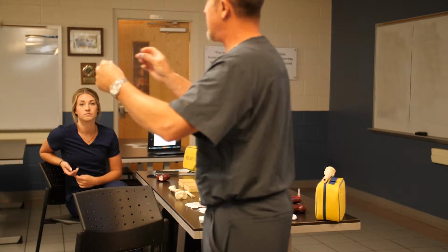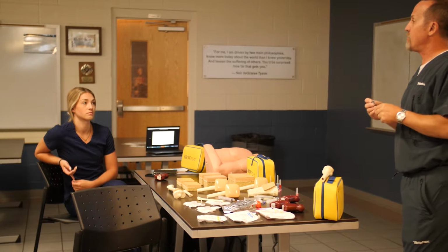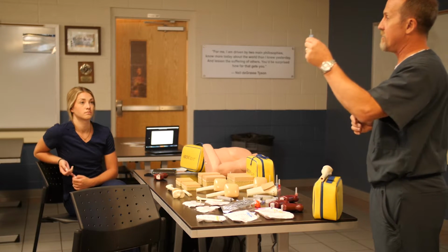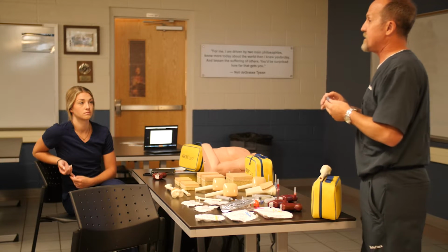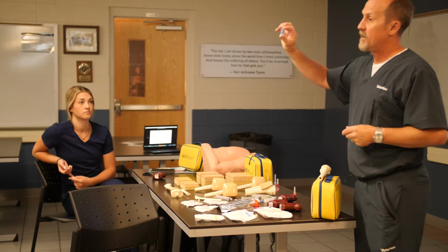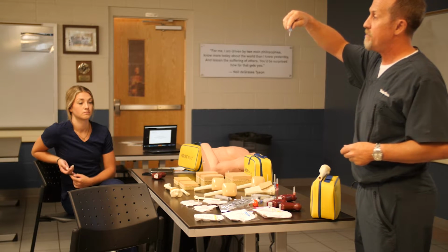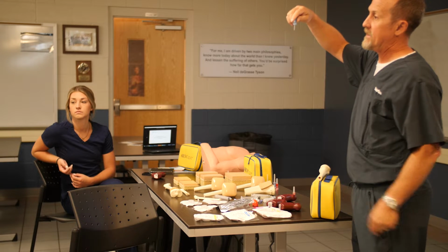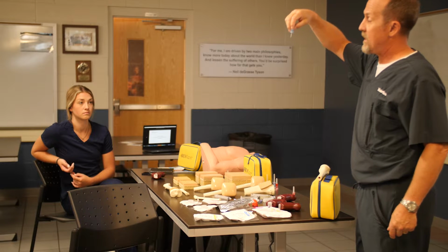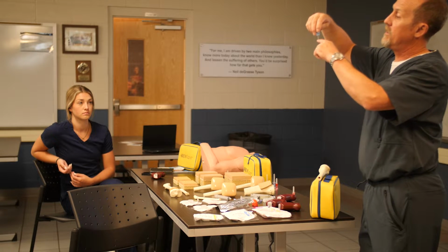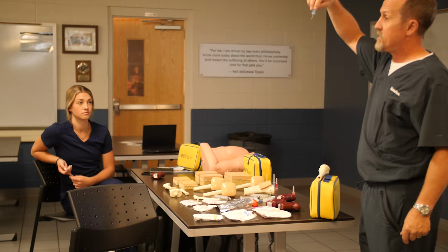Those black lines are intended for 2 purposes. Number one is to make you recognize that you do have a catheter in place before you insert this into a patient. I'll explain a little more about that in a second. The second reason for those black lines is they work as a depth gauge. After you've pushed through the soft tissue down to the bone, we want to make sure that we at least identify one black line above the soft tissue before we engage the driver.